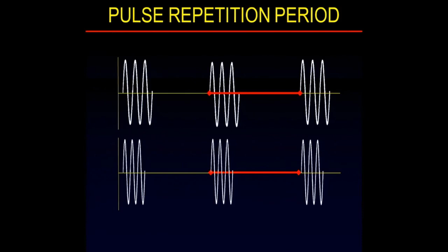So everybody listen. All of those had a PRF of 5 per second, 5 hertz. And this is where we want to break it down and make sure we use hertz. Because we'll say, okay, it's 5 hertz. 5 per second. What event are we talking about? The pulse. That's what we're talking about with PRF. Now, when we image shallow, the PRF sounds like this. High PRF. When we image deep, sounds like this. Low PRF. What determines the PRF? One thing and one thing only, how deep I image, and that's it. So that's the only thing that determines the PRF.